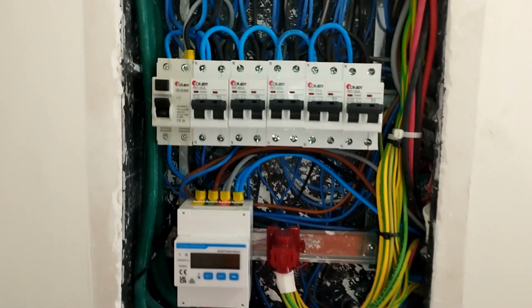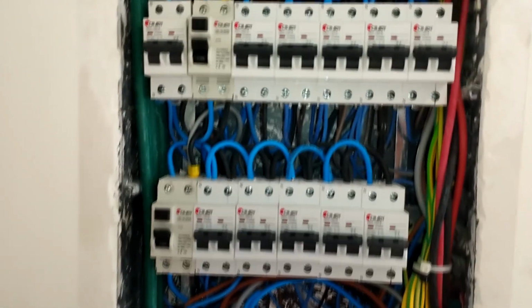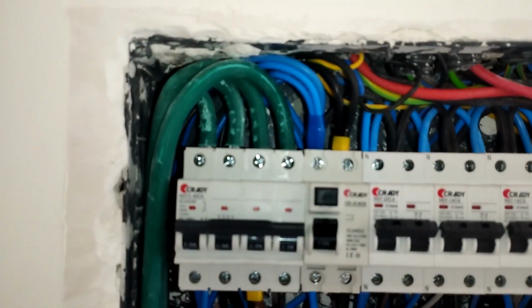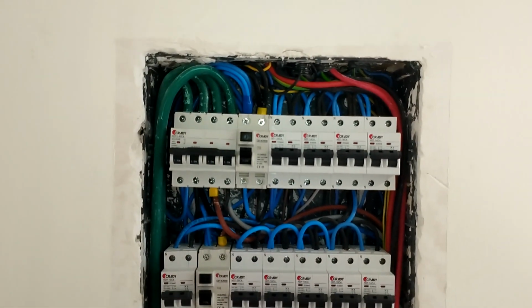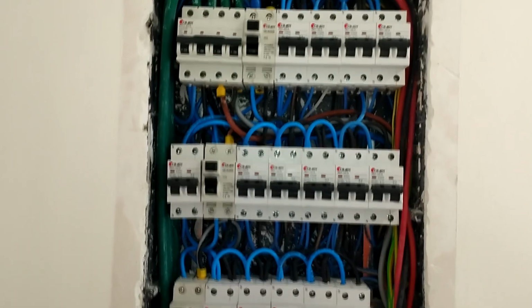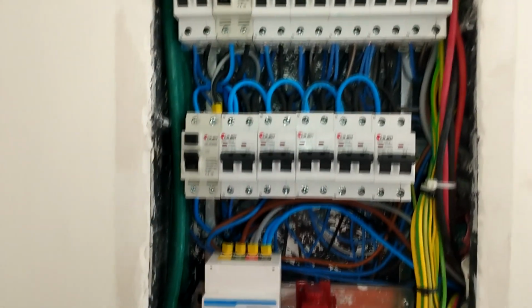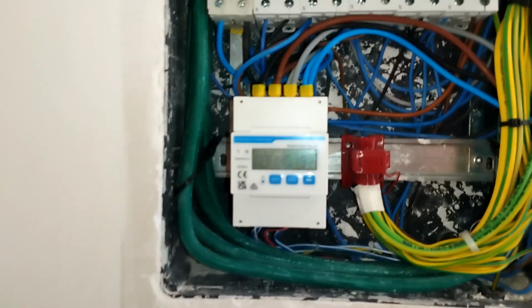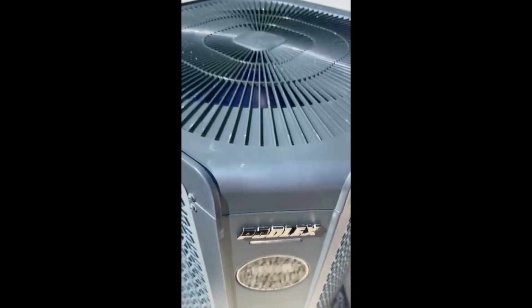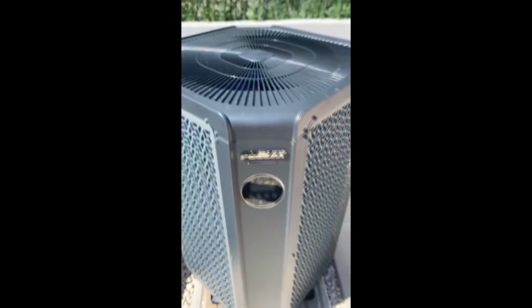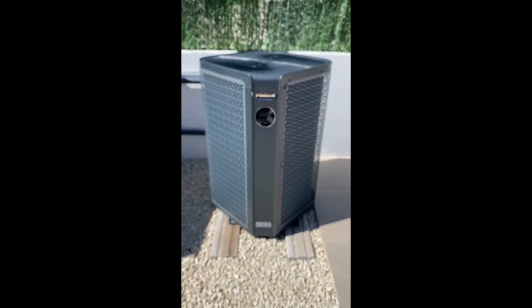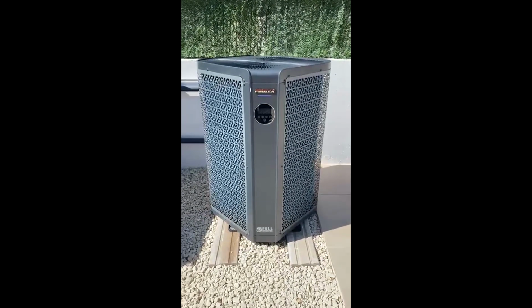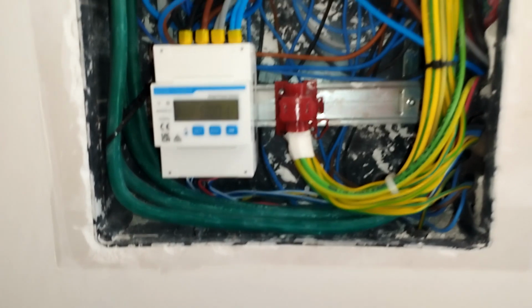A smart meter is similar to an electricity meter. It is connected to the solar inverter via a communication cable and provides information on how much energy the house is consuming, or conversely, how much energy is being exported to the grid. This information is critical for the proper functioning of the solar power system. Later, we will also be installing a three-phase heat pump for heating the swimming pool, which will require an additional protective device in this same distribution board. So we need space for that as well. But of course, we did find space for the smart meter.